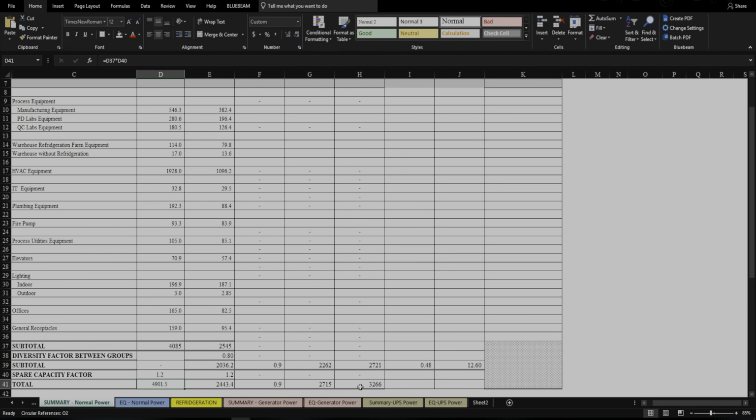Then, depending on what kind of service you want, primary or secondary, whatever your voltage is. So for my case, it would be 480 volts. Then I would use that to calculate the amperage, which gives me the switchgear size that we need. I guess we would keep using this spreadsheet as we move forward into detailed design, and I would update it based on whatever loads come my way.